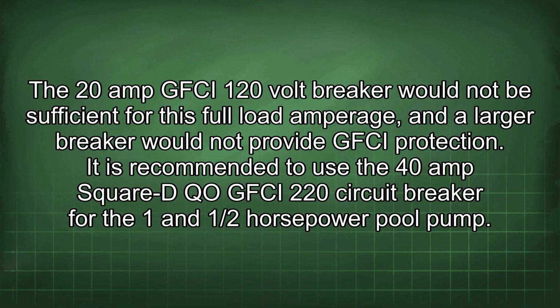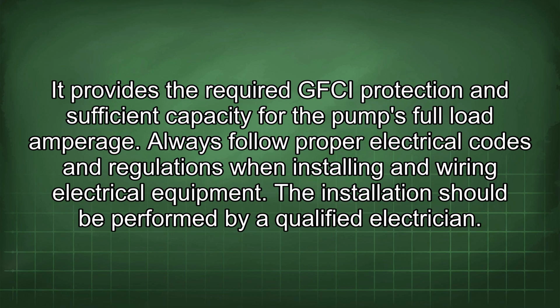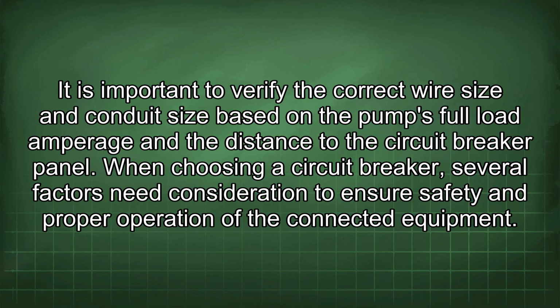It is recommended to use the 40 amp Square-D QO GFCI 220 circuit breaker for the 1 and 1/2 horsepower pool pump. It provides the required GFCI protection and sufficient capacity for the pump's full load amperage. Always follow proper electrical codes and regulations when installing and wiring electrical equipment. The installation should be performed by a qualified electrician. It is important to verify the correct wire size and conduit size based on the pump's full load amperage and the distance to the circuit breaker panel.